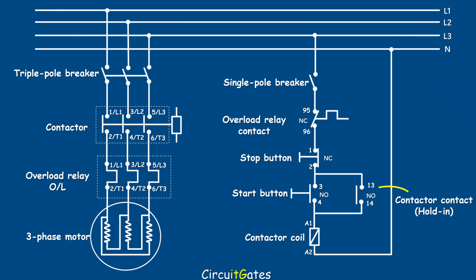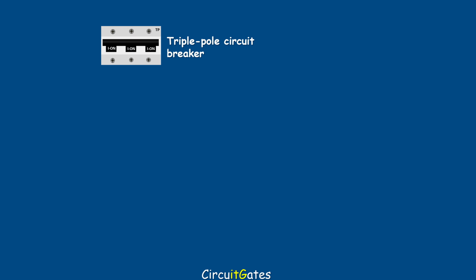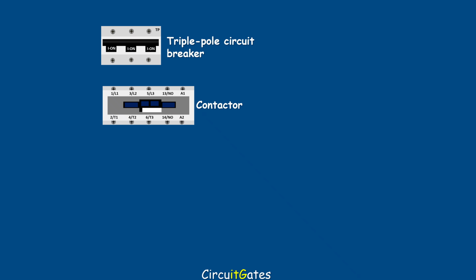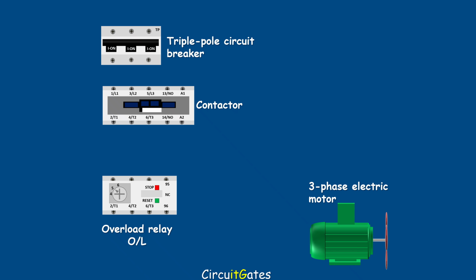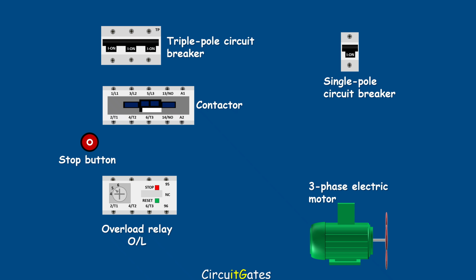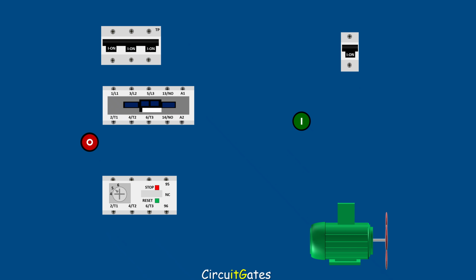If you are unsure about installing the direct online starter, you just need to follow the numbers we have shown on the circuit diagrams. As we have said earlier, on the power circuit, we have a triple pole circuit breaker, a contactor, an overload relay, and an electric motor. The control circuit consists of a single pole circuit breaker, a stop button, a start button, and contacts on the power circuit components. When wiring a direct online starter control circuit, we take the live wire from the supply and connect it to the single pole circuit breaker. From the single pole circuit breaker, the live wire goes to the overload relay. From the overload relay, the live wire goes to the stop button.